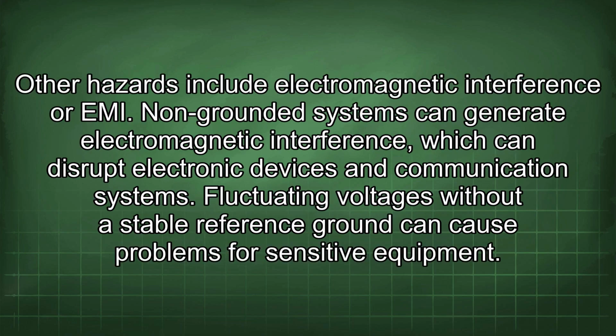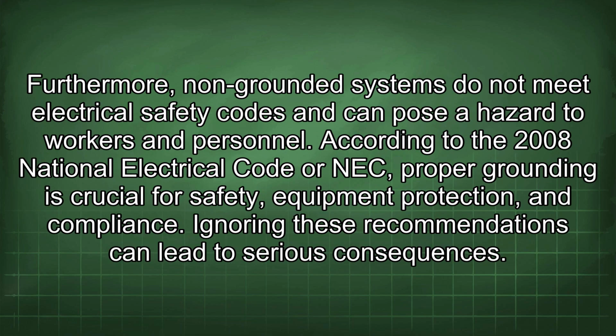Other hazards include electromagnetic interference, or EMI. Non-grounded systems can generate electromagnetic interference, which can disrupt electronic devices and communication systems. Fluctuating voltages without a stable reference ground can cause problems for sensitive equipment. Furthermore, non-grounded systems do not meet electrical safety codes and can pose a hazard to workers and personnel.